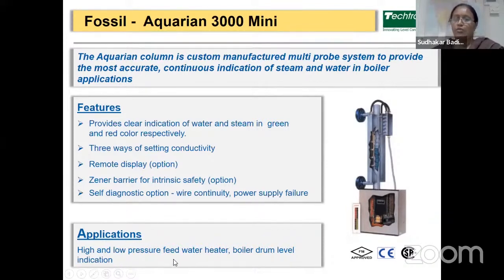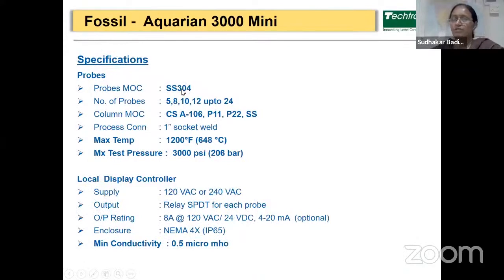Applications are high and low pressure feed water heaters, then boiler drum level indications. Probe MOC will be SS304. Number of probes will be 5, 8, 10, and up to 24 numbers. Column MOC will be CSA106, P11, P22, or SS. Suitable for maximum temperature up to 1200 degree Fahrenheit and maximum test pressure of 3000 PSI. The display controller will have a supply of 120 volt AC or 240 volt AC.